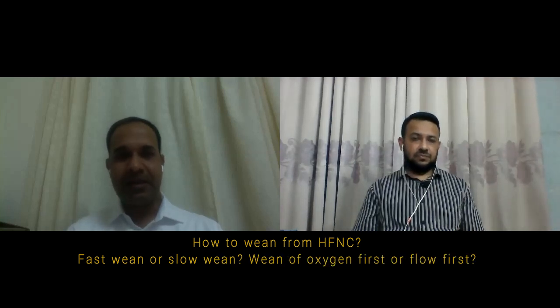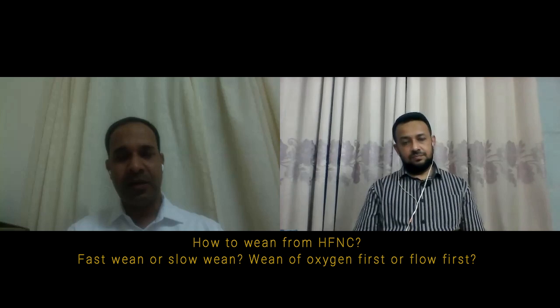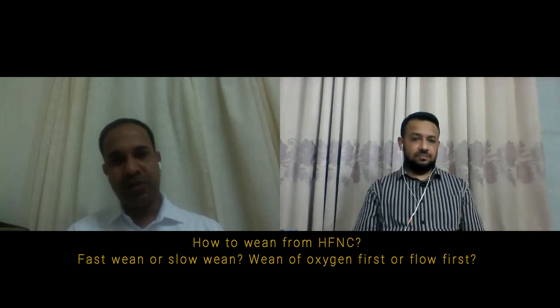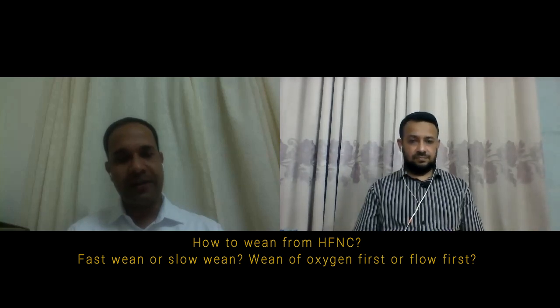For example, someone who's on 20 liters per minute flow will reduce to 15 liters after 6 to 8 hours of stability. And every 6 to 8 hours, we keep coming down 25% till we reach 0.5 liters per kilo. And at that point, we simply change it to standard nasal cannula oxygen.